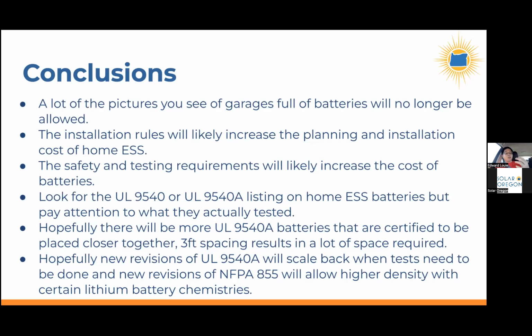And also keep in mind that the NFPA 855 standards and these UL test standards are not necessarily set in stone. These are the current rules. Future committee hearings might find that the industry has come back and determined that we've gone overboard with safety, and that in real life, we don't need to go to this level in order to be safe. And so there could be future versions where it's less arduous and difficult to properly place the batteries according to the current rules. There may be that future.